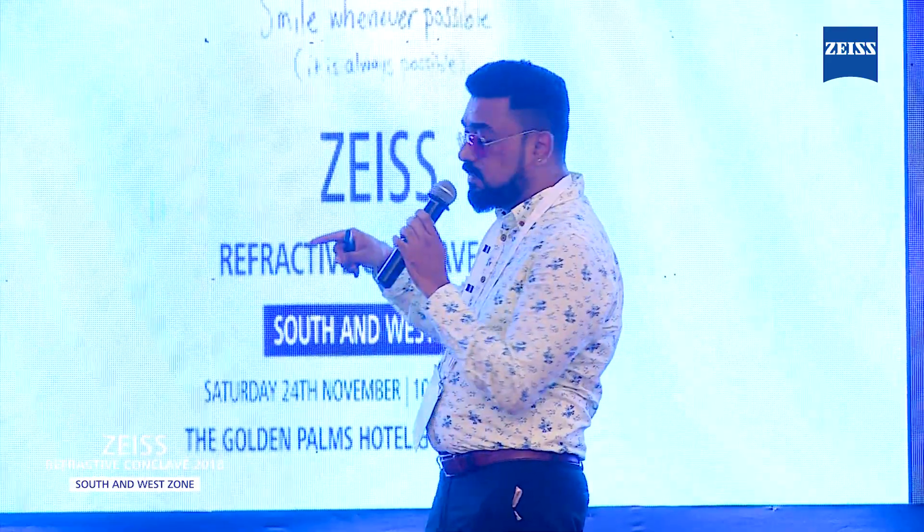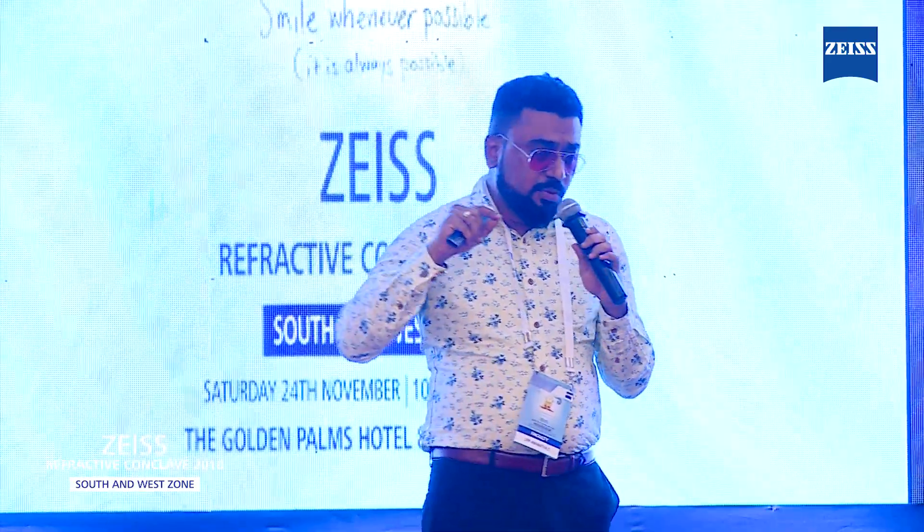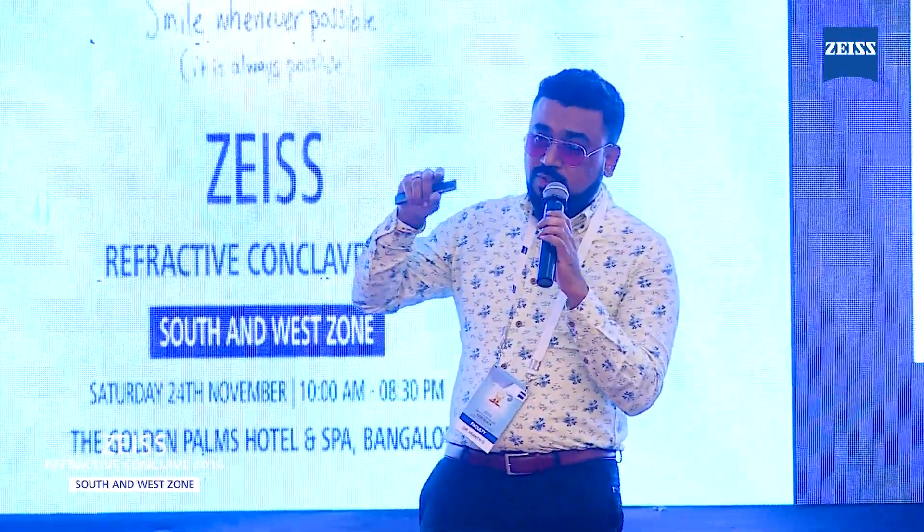Importance has to be given to the energy setting. As you can see here, it's around 32. The amount of energy delivered with Visumax onto the cornea is between 120 to 170 nanojoules. At a setting of 32, we apply around 155 to 160 nanojoules onto the cornea. If lenticule separation is very difficult at 32, we may increase the energy to 34 or 36 — this can cause more inflammation, apoptosis, or edema, which subsides with steroids. If it works well at 32, we can still reduce to 31 or 30 and go ahead; otherwise it remains prefixed for the rest of the cases.